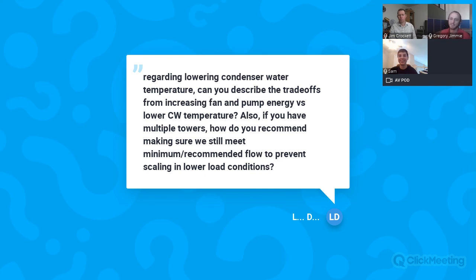I'll jump into it, and then if Jim, if you want to add to it, feel free. I'll start off with the minimum flows. The safe answer is to hard code a minimum on your pumps that corresponds to that on the towers. So if you've got 1,000 GPM minimum that those towers require, usually you can reach out to your cooling tower manufacturer, and they'll give you the range in which those towers can operate. I believe California has like a 50% turn down requirement. So that's not unheard of. So let's just say that that's kind of going to be the standard if it's not currently in your facility. But 50% turn down on your towers is usually pretty safe.